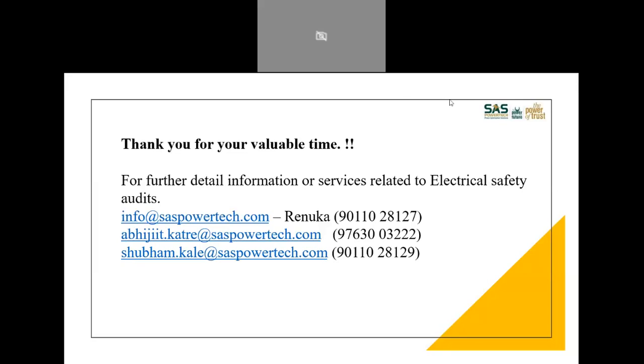Second thing is use or misuse. Even that will decide the life of electrical equipment. It will also depend upon the atmosphere in which you are using it. We have a few clients in chemical zones in India where in a few plants the ambient is so corrosive that unless filtered air is given to electrical panels, they can go bad. So it is very difficult to say, but on an average, a well-maintained and type-tested electrical equipment should last somewhere between 15 to 20, 20 to 25 years.